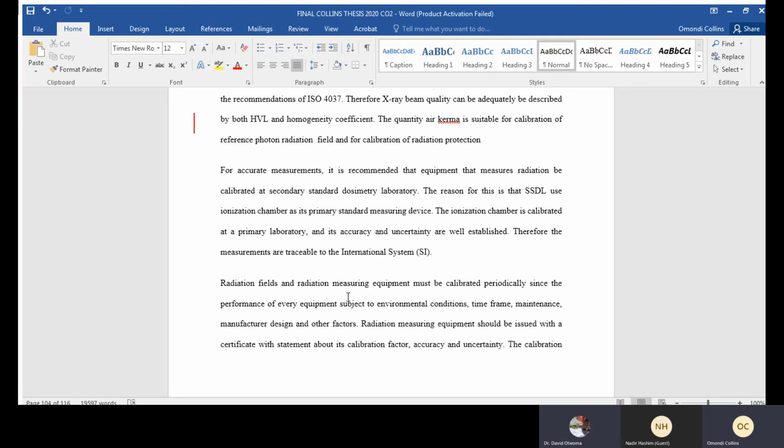Collins, yes, since this is your research and it needs to have an impact, you can also say that the calibration of ion chamber is mandatory to fulfill the legal requirement and IAEA recommendations to ensure that the measurements are compatible with those made elsewhere and to assure constancy to promote customer acceptance. Thank you. Actually, that's exactly the reason why we do this, that any measurement done in the dosimetry laboratory should be the same as the one that is done in another country.